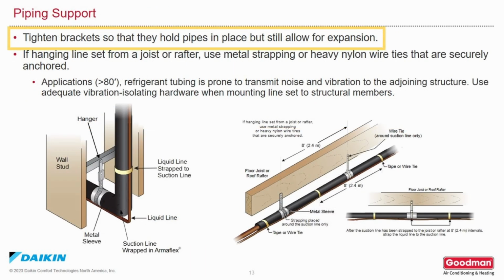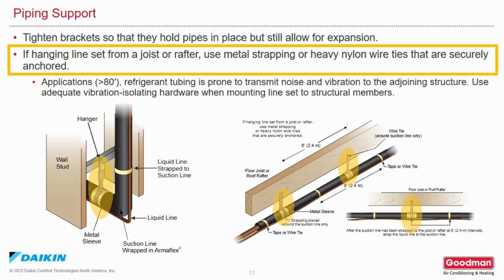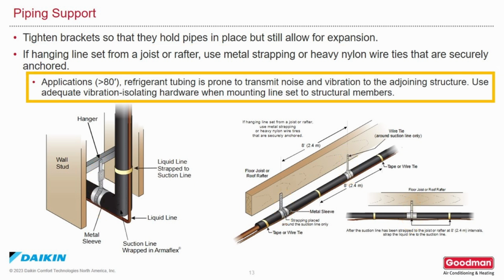Support the refrigerant piping with brackets that will hold the pipe firmly but still allow for expansion. Use metal or heavy nylon wire ties to securely anchor your line set. If the application is more than 80 feet of refrigerant lines, the tubing is prone to transmit noise or vibration to the structure because of pulsation in the line set. Make sure you use adequate vibration-absorbing hardware when you are mounting the line set to the structure.